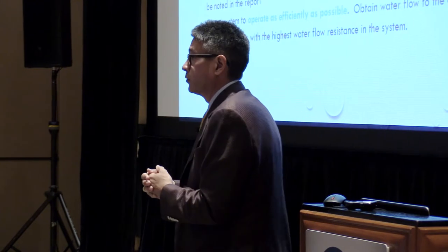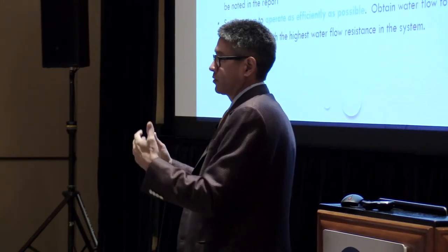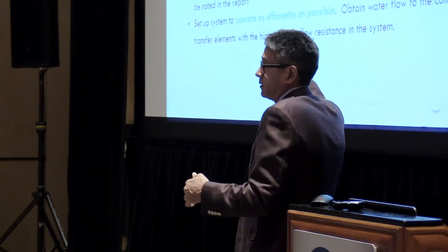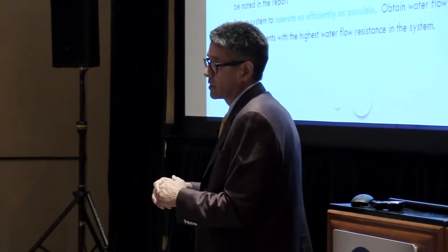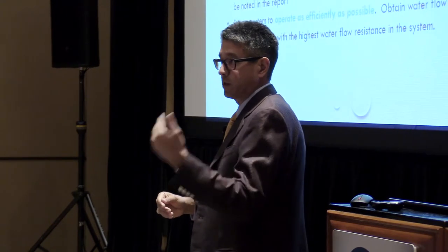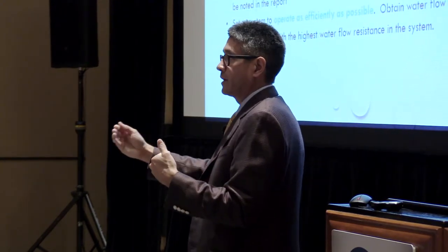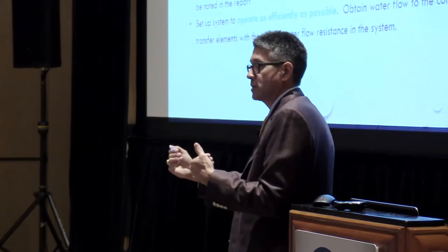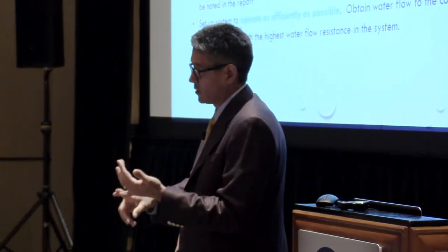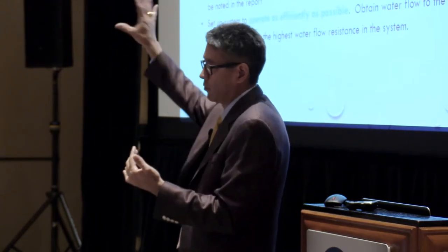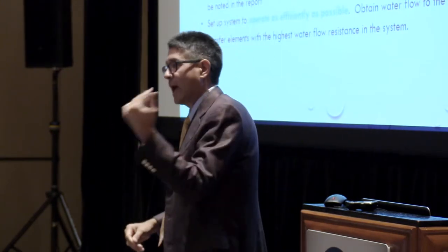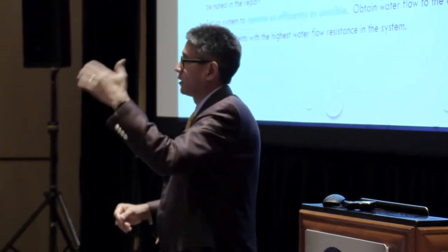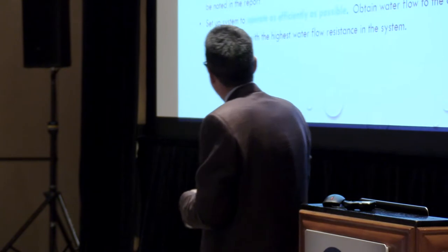And then as we're working through the system, if you're doing a temperature test, you're doing some spot checks, the big thing is look at your differential pressure operating set point. See where it is, see what it's doing, make sure you're getting water flow to your worst case coils. A lot of times by just looking at those drawings, seeing where your largest load is, typically the engineer has the farthest point in the system, as we know. So how can we get water flow out to that coil? And if so, how can I do it with the lowest operating set point possible?